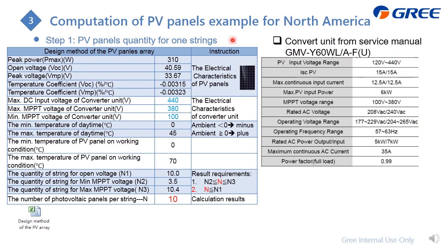So from this selection table, this part you need to input the parameters of these PV panels, including this Pmax and the other 4, and also this one you can get from here, and input to here. And then this one is your local temperature. You need to input it, and in the end it will automatically come out how many panels for one string. From this calculation it is 10.